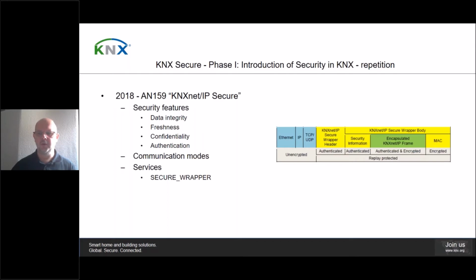Further, the secure information also contains a KNX serial number of the sender of the wrapper frame, or it contains a message tag 00H for Unicast or an arbitrary value for multicast. This makes that two messages sent shortly after each other can be differentiated and are not seen as a replay attack. The message authentication code is a 128-bit encrypted CBC MAC.